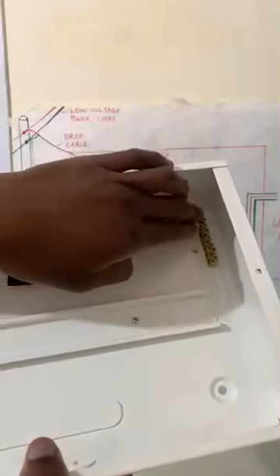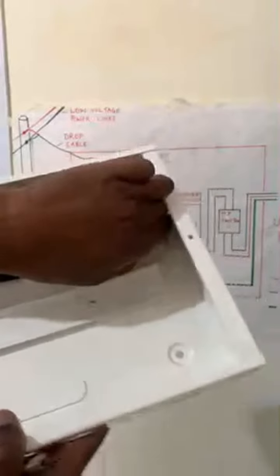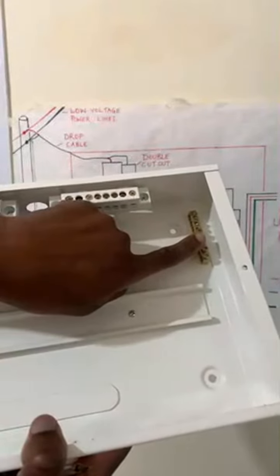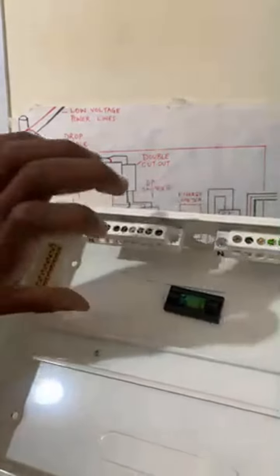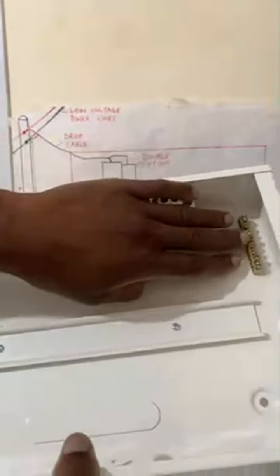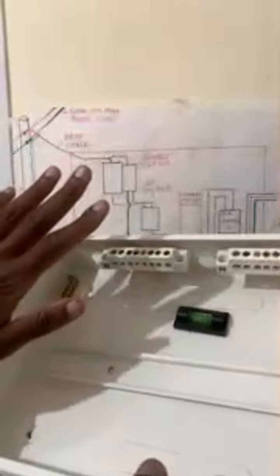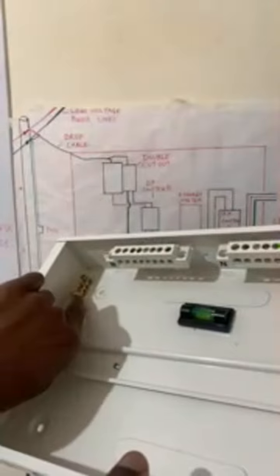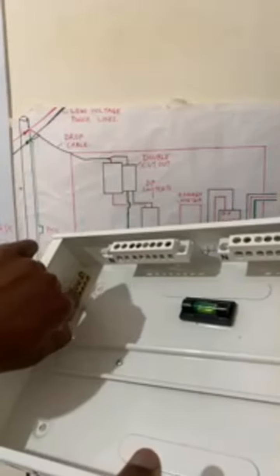But what I'll do, I'll first of all bond these two, the earth bar that is on this far end as well as the earth bar that is on this far end, and then connect them together. Remember, at the consumer unit, you must not link the earthing connection with the neutral. That is after the energy meter, like we have rightly put it. So the earth connection will be connected here.